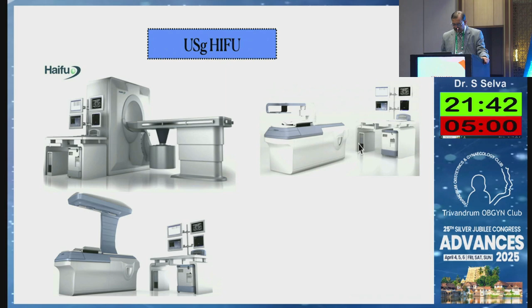There are several differences between performing HIFU with MRI compared to ultrasound. Now, we know that MRI-based HIFU has very good anatomic resolution. There's no question about that, as opposed to ultrasound. There's also something called temperature monitoring for MRI-based HIFU, which is not available in the ultrasound-based HIFU. However, the advantage of the ultrasound-based HIFU is that the transducer movement is much more compared to the MRI-based HIFU. Also, as you can see, this is in a tunnel and this is in an open concept. The patient positioning is far better with the ultrasound-based HIFU than the MRI-based HIFU.